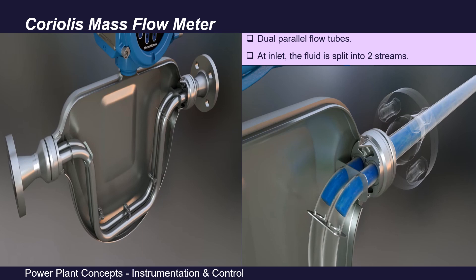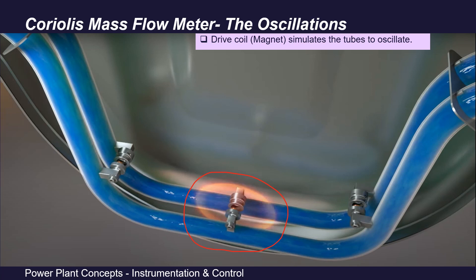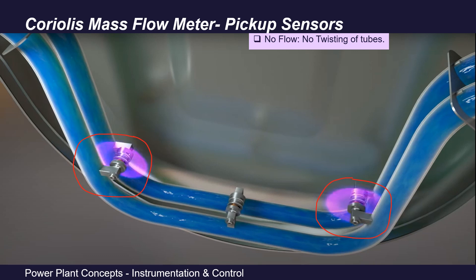As we can see in this picture, the flow meter has dual parallel flow tubes. When the process fluid enters the flow meter it is split into two parts — half of the fluid passes through each tube. During operation, a drive coil stimulates the tubes to oscillate in opposition to each other at the natural resonant frequency of the tubes.